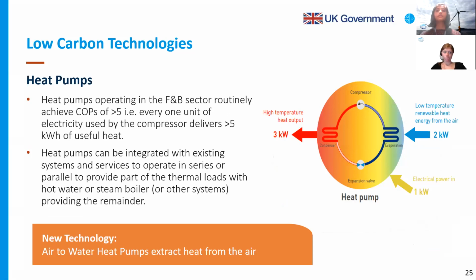Heat pumps. So we did mention heat pumps in one of the surveys in the Mentimeter. Heat pumps are typically electrically driven. They help to transfer heat from a low temperature environment. Low temperature means a low quality heat source, such as your ambient air, low grade heat, water, maybe condensate water, or other waste heat that you can recover, and raise it to a higher quality, higher temperature heat for useful applications. This is made possible through a typical refrigeration cycle. You can see on your right hand side.